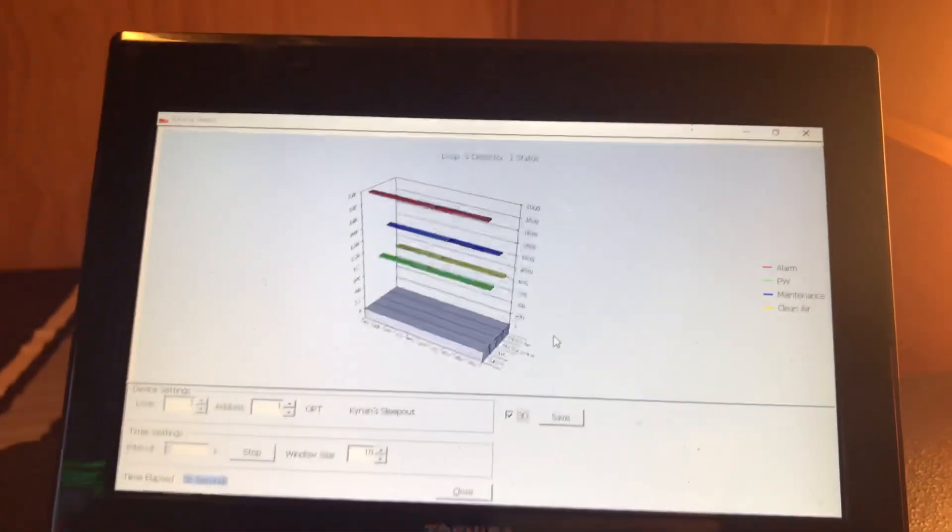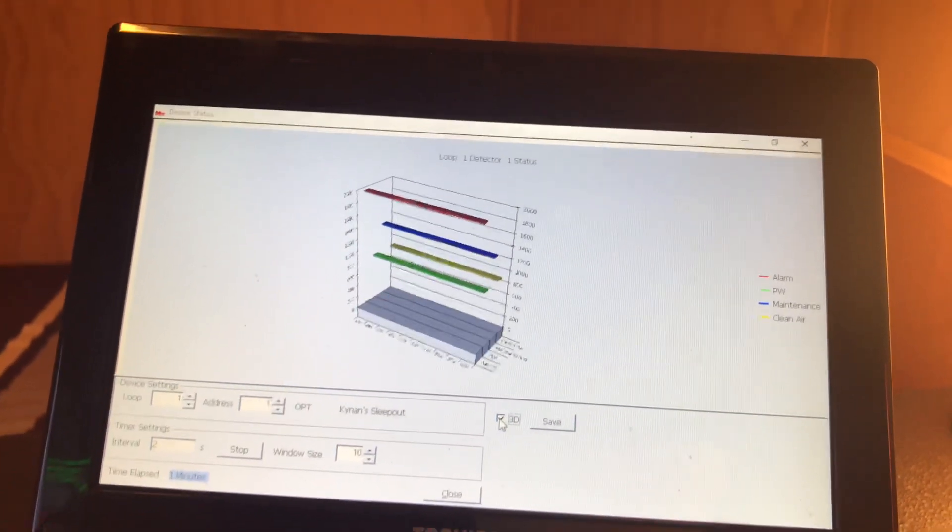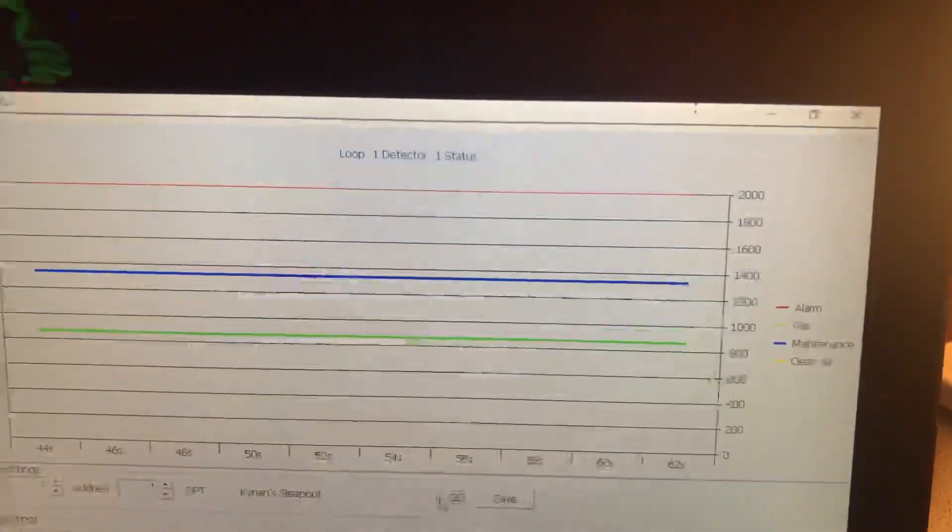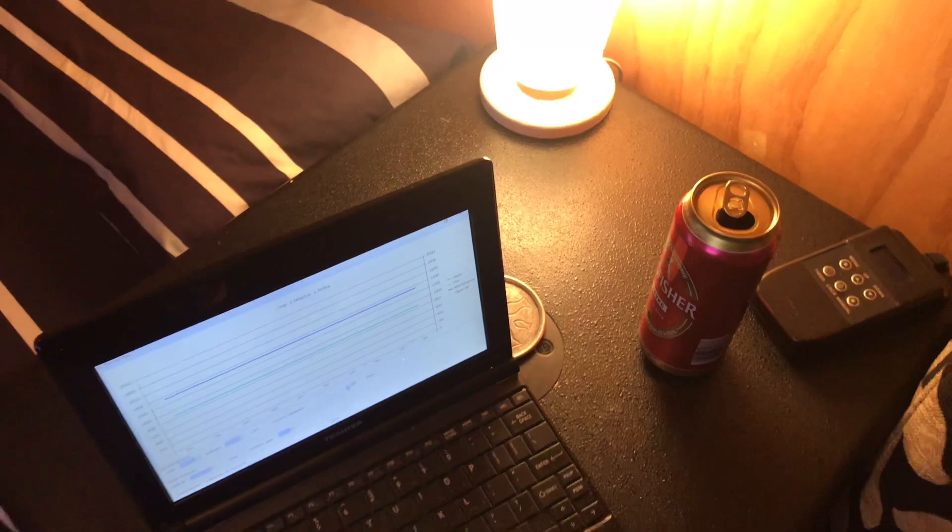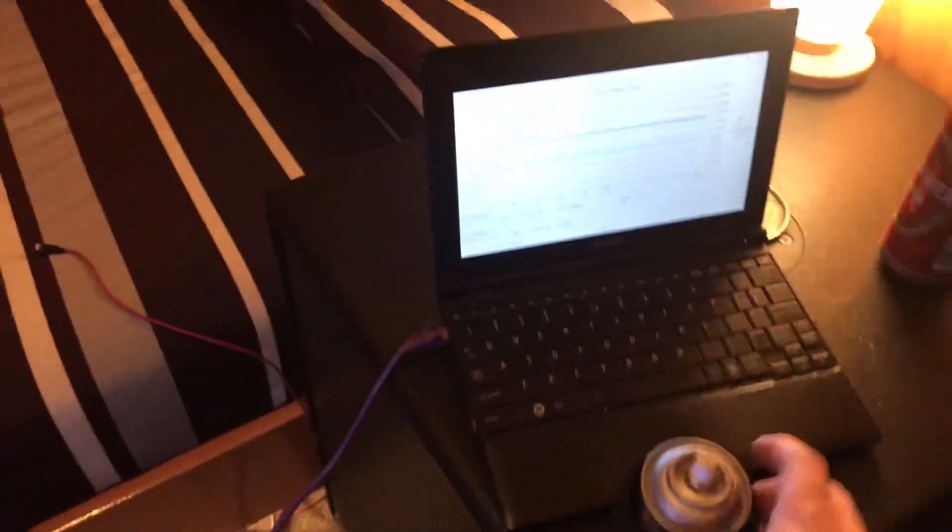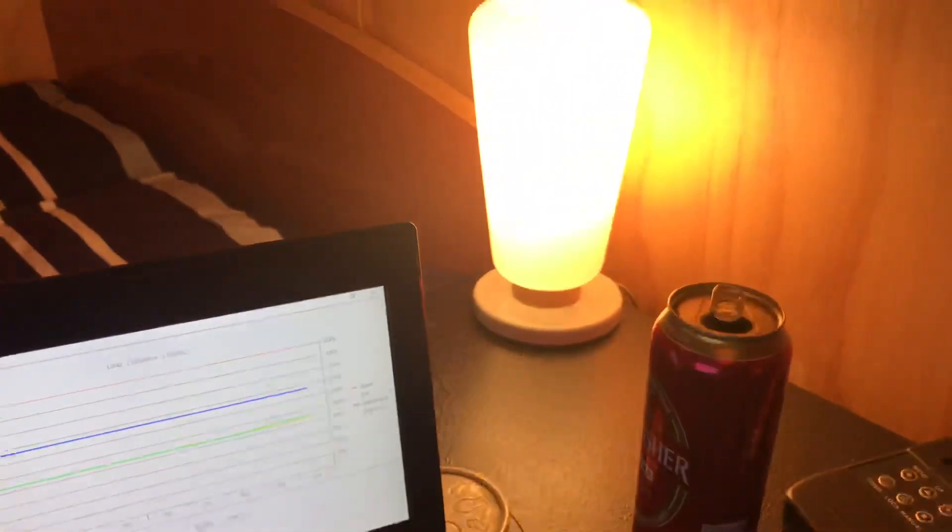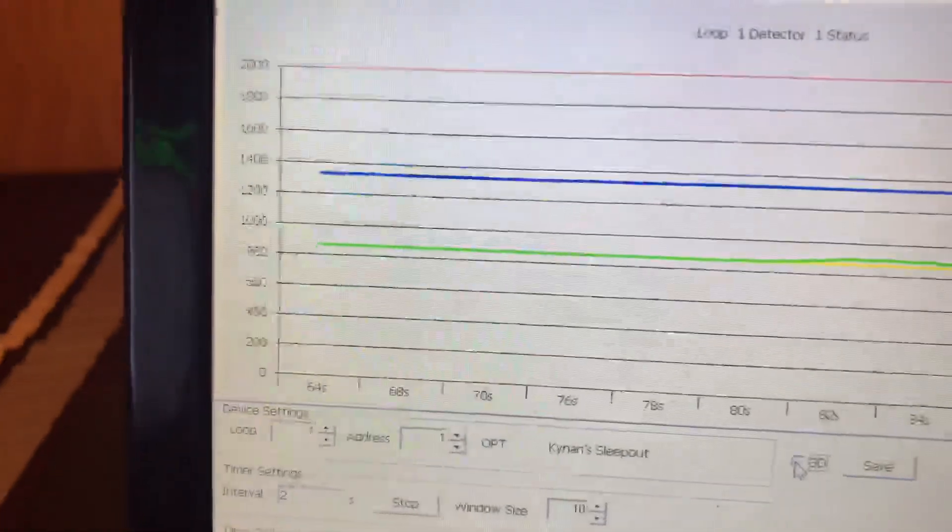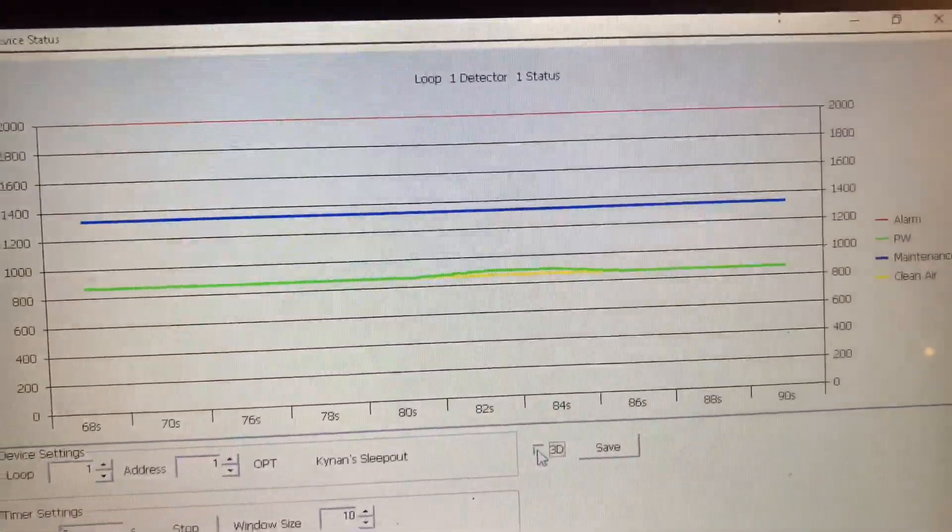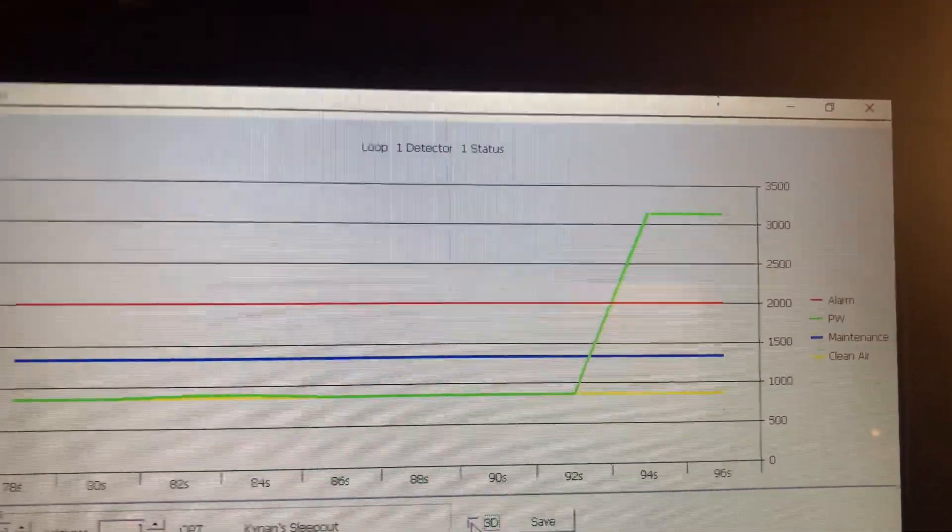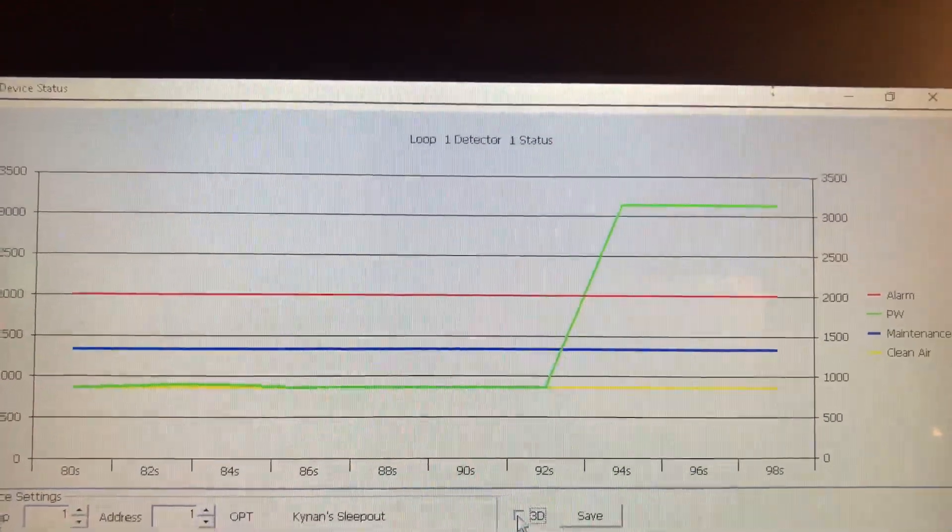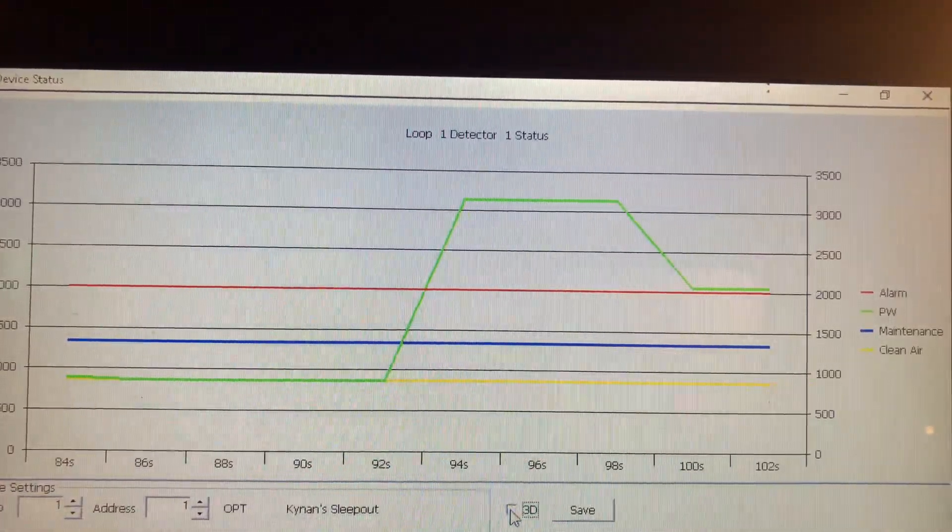Let's actually test the smoke alarm now. Make sure the panel is still in silence. We'll take it off 3D for an easier view. And we will get some smoke. Looks a bit hard to see the screen at the same time. We will just turn off the bedside light quickly if I can. Actually, I'll just try to do this one-handed. So I've just sprayed a tiny bit of smoke at the moment. And you should... yeah, there wasn't much that got in there, but you can see the value of the smoke alarm just shot up way past alarm value, but now it's coming down very quickly.